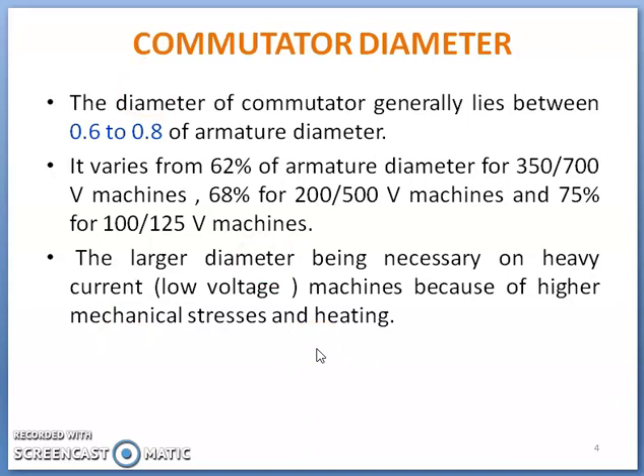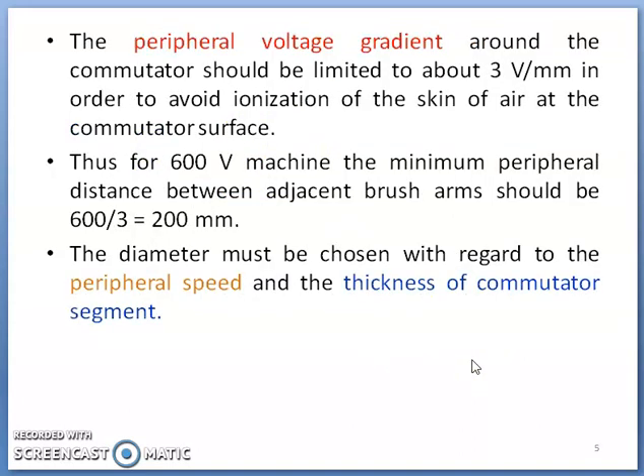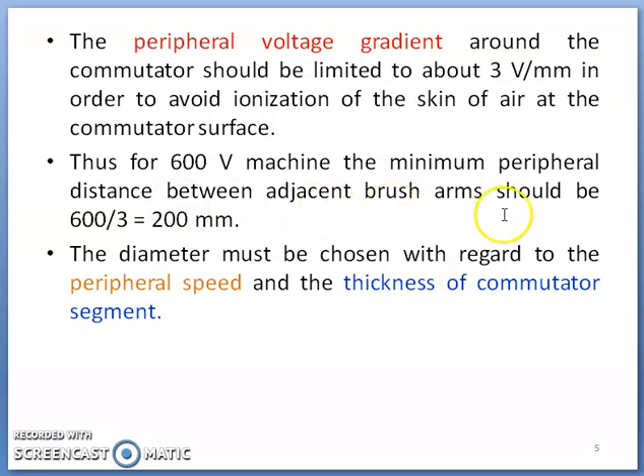Machines can be designed for high voltage–low current or high current–low voltage applications depending on the winding type, and the commutator diameter may exceed 0.6–0.8 of armature diameter in such cases. The peripheral voltage gradient around the commutator should be limited to about 3 volts per mm to avoid ionization of air at the commutator surface. For a 600-volt machine, with a gradient of 3 V/mm, the minimum peripheral distance between adjacent brush arms should be 200 mm.